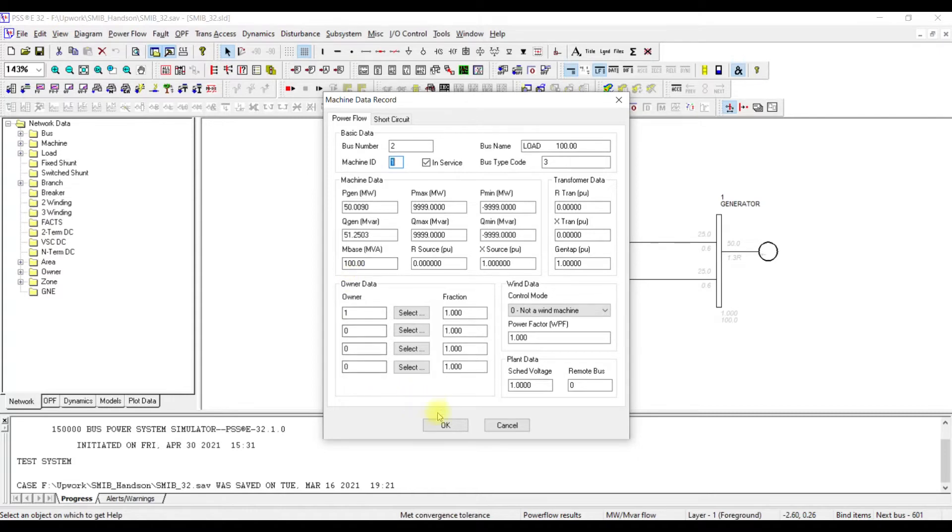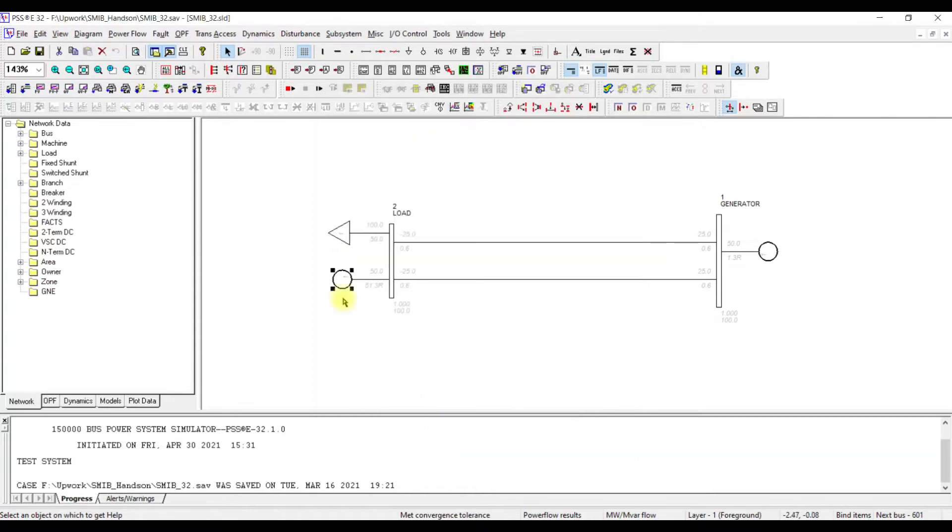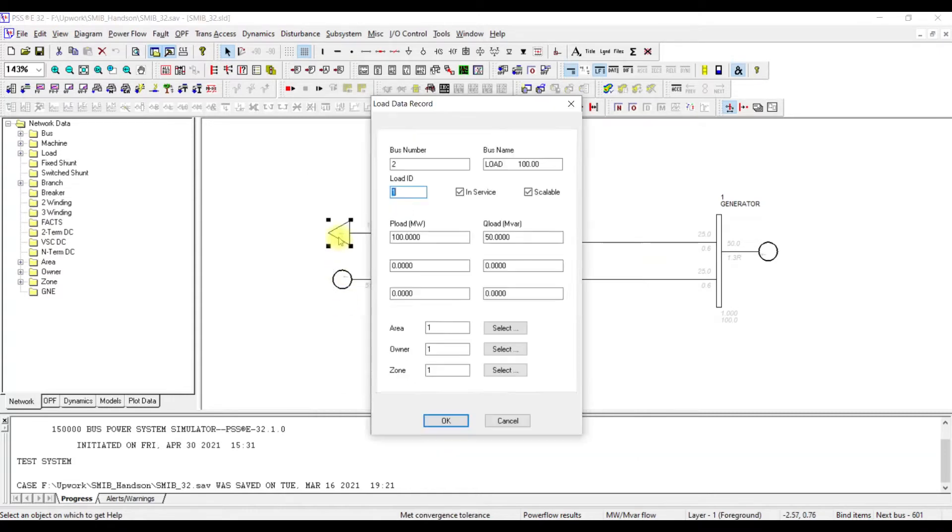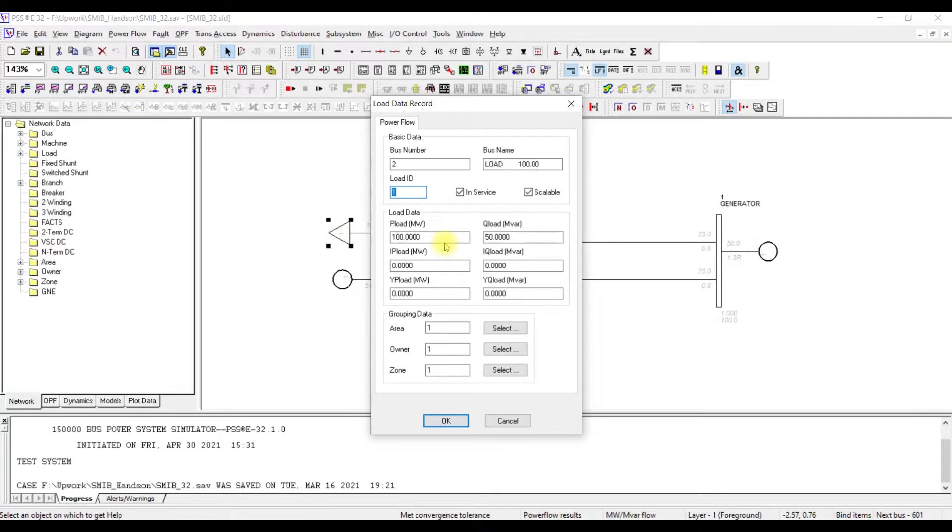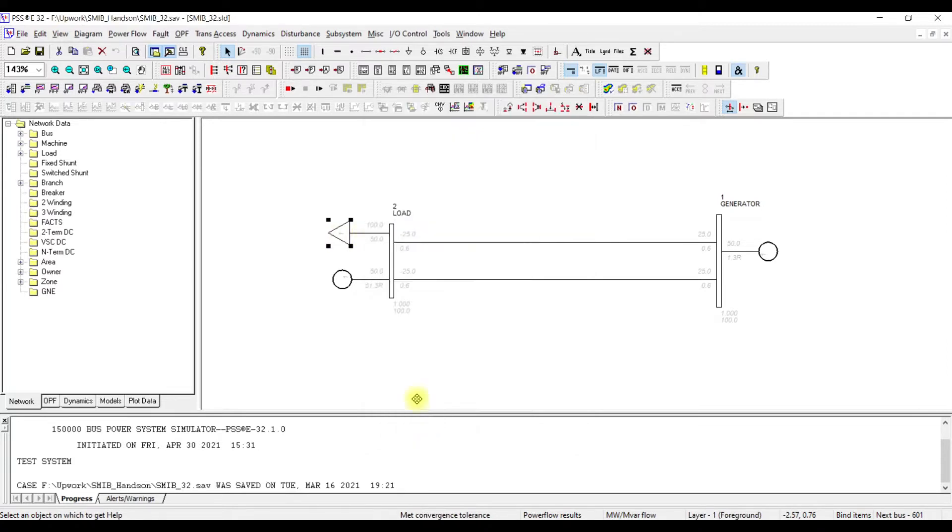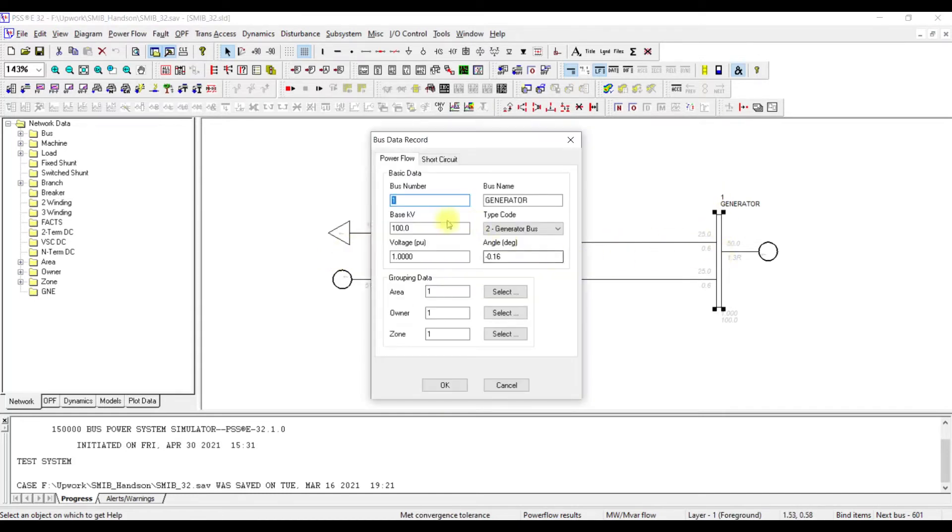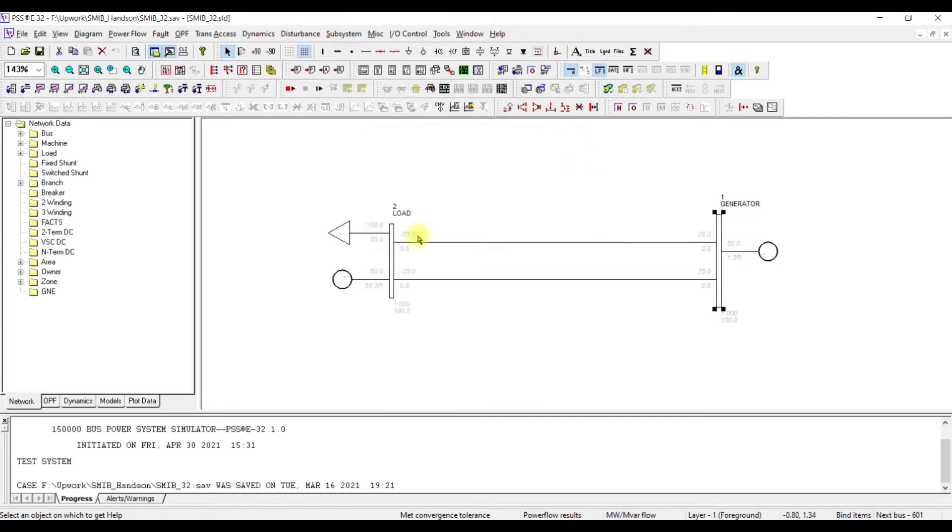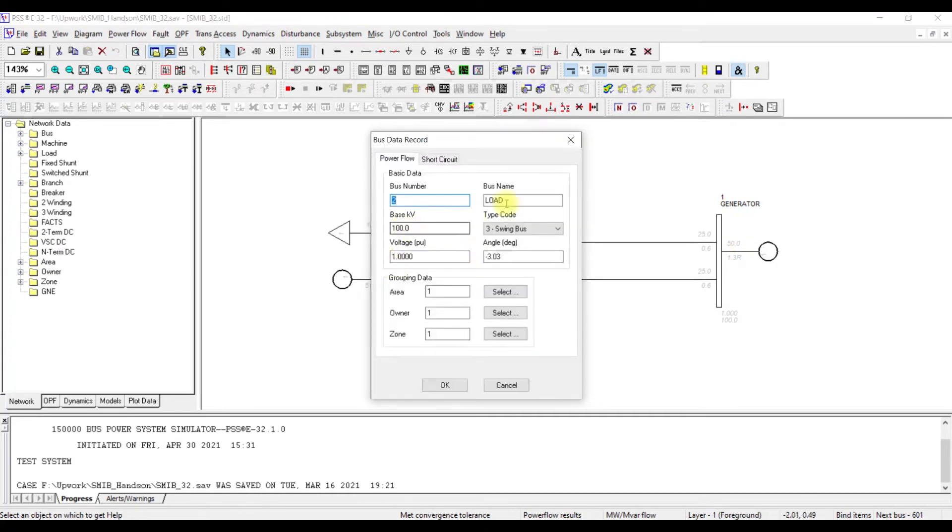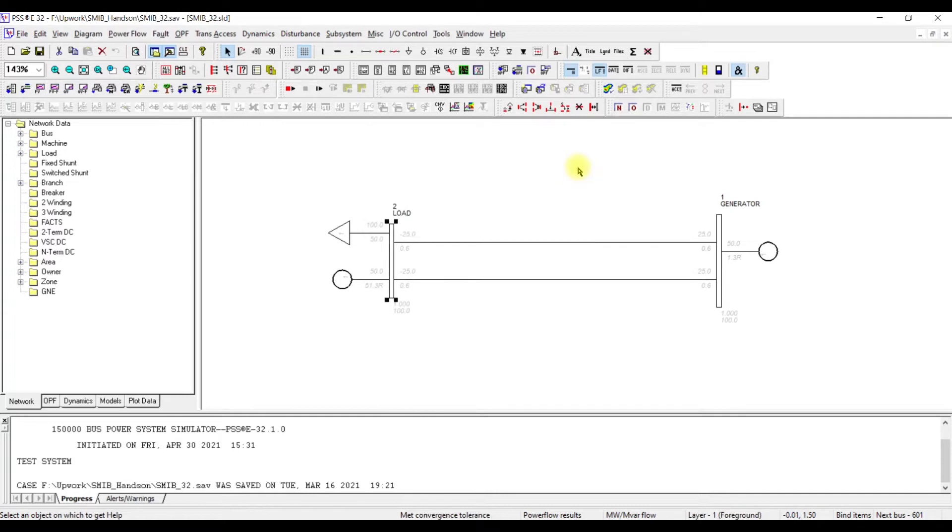Why we haven't provided? Because we are assuming it to be an infinite bus and however the reactive power is required by the system, this is going to be provided by this bus and its source we haven't changed. You can use x-source equal to 1 at 100 MVA base. Nothing has been changed here. First of all, you are going to create this. Then, we have assumed a load here of 100 MW and 50 MVAR. You can create a load on this bus. Then, this swing bus is connected to the generator bus which is also at 100 KV.